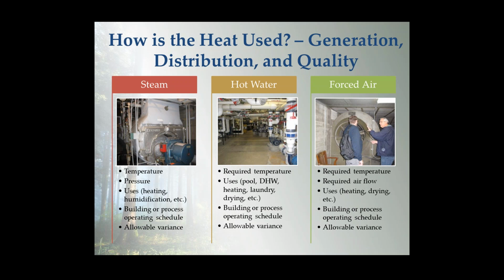If it's a hot water system, what temperatures are needed at different parts of the building and for different uses, whether it's simply heating a pool, providing domestic hot water heating, or drying at a laundry? All those things come into play. What is the building or process operating schedule? When do you need the highest temperature water? Are there different zones that are going to need different temperatures at different times of the day? And what are the restrictions, as far as plus or minus 5 or 10 degrees, to those requirements?